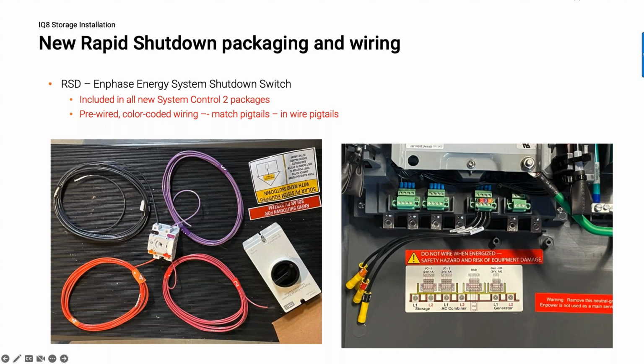Now, if you were to miswire this and 1 and 2 are not connected, or 3 and 4 are not connected, the system is actually going to be in a rapid shutdown state, and so the system relays won't close properly, so it won't be in the proper configuration. So the way to test this actually is when you put this into operating mode, which is like in the vertical position.